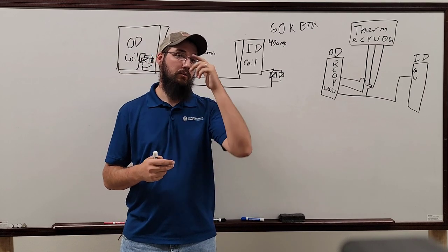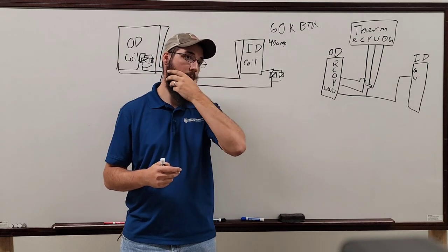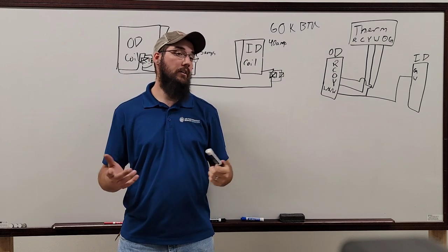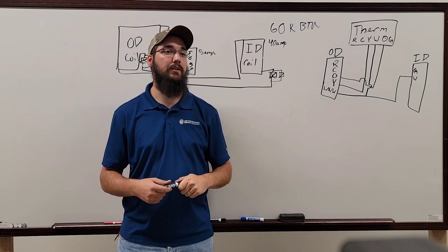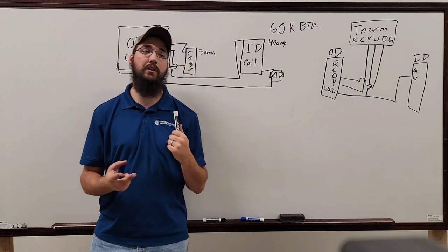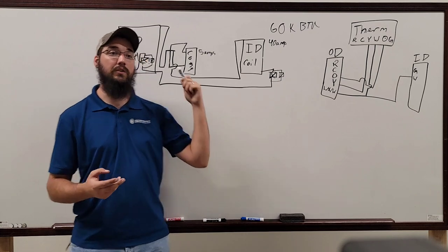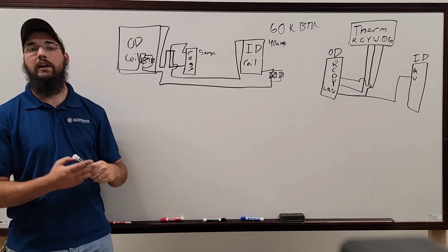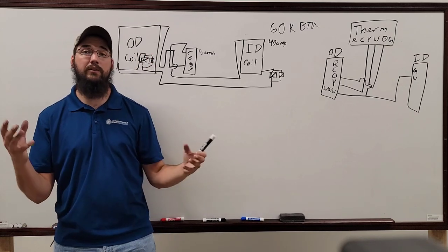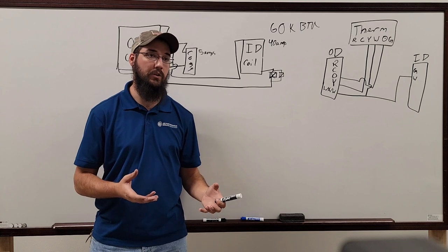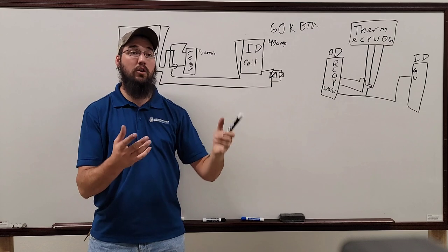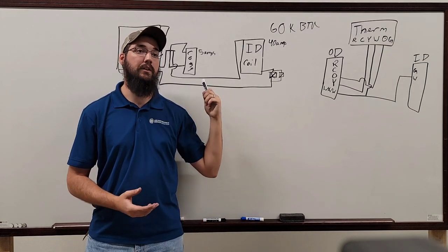I was just saying that it's probably, like you're saying, not very common because we don't get that cold very much. No, it definitely happens. Especially if the heat pump starts to struggle with charge issues, or if there are any kind of airflow issues, or say we're not defrosting properly, anything of that nature, it's not too uncommon. It's a matter of do you catch it happening more than anything. But it's not too uncommon to have, on our cold days, both of them run together.